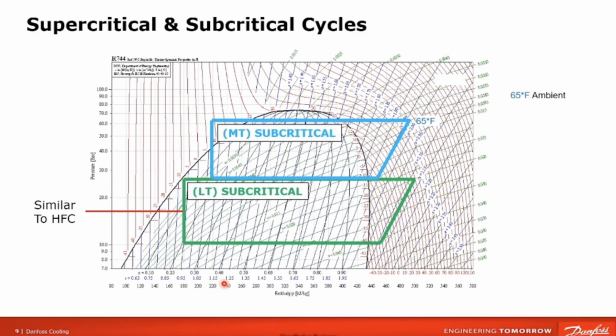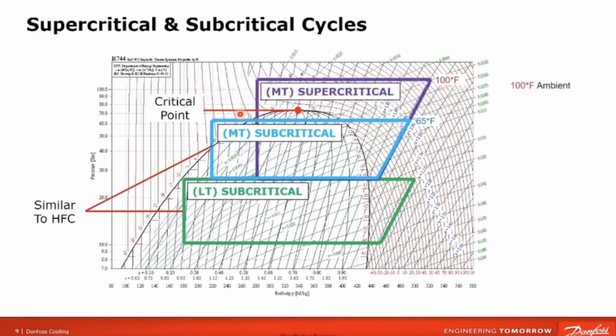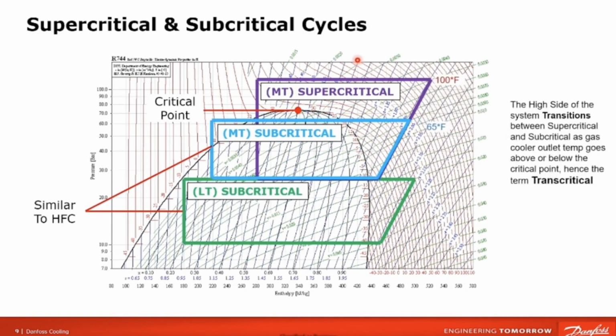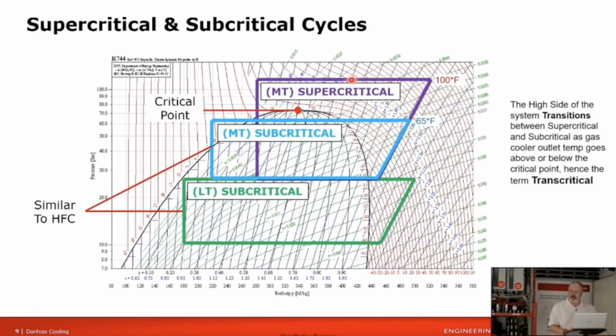It's still similar because we're below the critical point, and we are actually making liquid in the gas cooler, in the condenser. Where the difference comes in from HFC is when we're above the critical point of 87 degrees. Now the high side of our system is in the supercritical region. So now we're in the supercritical region. So a CO₂ system will, in a high ambient, operate the high side in the supercritical fluid region.